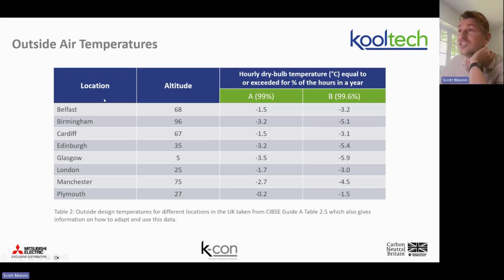So, first consideration when we're running a selection, and I'm going to do a live demo as well, so don't worry if this doesn't all land straight away. The first thing we're going to have to take into account when working on an application for a building is our outside design temperature. The reason for that is the outside design temperature directly translates to a product's efficiency and kilowatt rating at that point in time. And you'll see this in a moment.